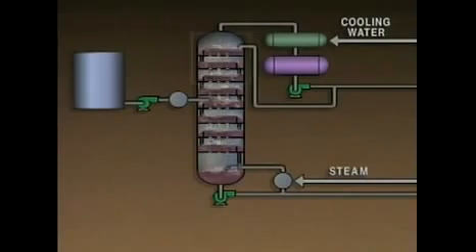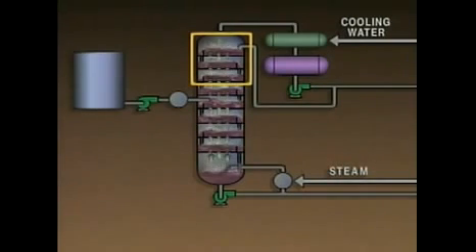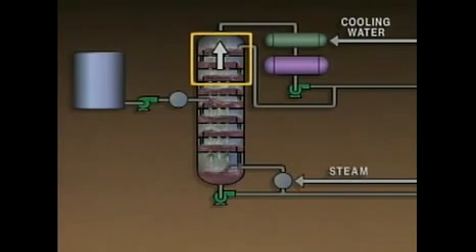We'll begin with the temperature at the top of the tower. The temperature at the top of the tower should be at or slightly above the boiling temperature of the desired overhead product at the operating pressure of the tower. If the temperature at the top of the tower is higher than it should be, more of the heavier components will vaporize and become part of the overhead product instead of flowing down the tower as a liquid.